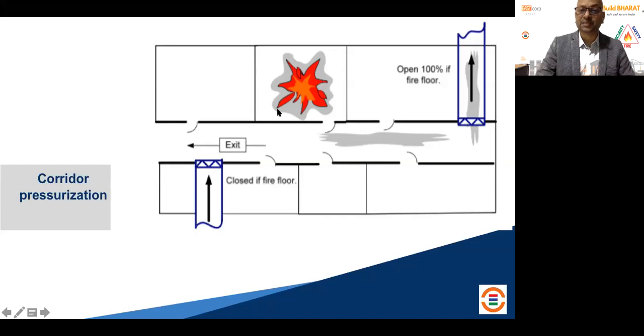So if this area is under fire, this room specifically is under fire, and this room is connected to this corridor, what I am going to do is make this corridor negatively pressurized. So you are going to open this damper to allow the smoke to go out. At the same time, we are restricting the supply from here. So when you are creating this zone as supply and return duct, you are placing those smoke dampers on the duct in such a way that the fire alarm system will activate this opening and closing automatically. This is opening and closing. And that's how you manage the smoke. So the smoke remains confined to this floor only. It doesn't travel through any ducts, through any HVAC system which is centralized, where it would cause more damage.